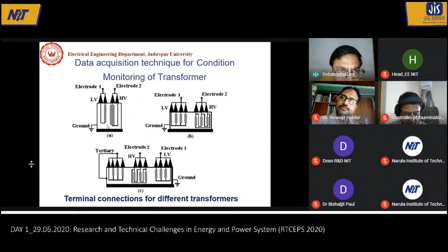Again, if we short circuit them, the insulation which was being charged will discharge. That means there will be some capacitive discharging. That is why the terms polarization and depolarization current are used. Polarization means charging current and depolarization means discharging current. From that current, we can develop a model.